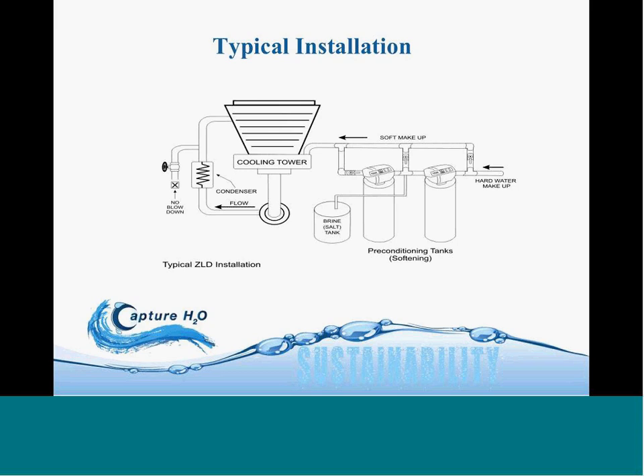So a typical installation would look like this. If you remember that slide earlier, how many more moving parts were on that, this is the basic system that we need to run this program. We install a high efficiency pretreatment system on the cooling tower makeup, allowing us to remove 100% of the minerals going to the cooling system. With that, we can operate the system. We do have blowdown controllers and other stuff that we put in here, mainly for performance monitoring, but this is the basis of what we would need.